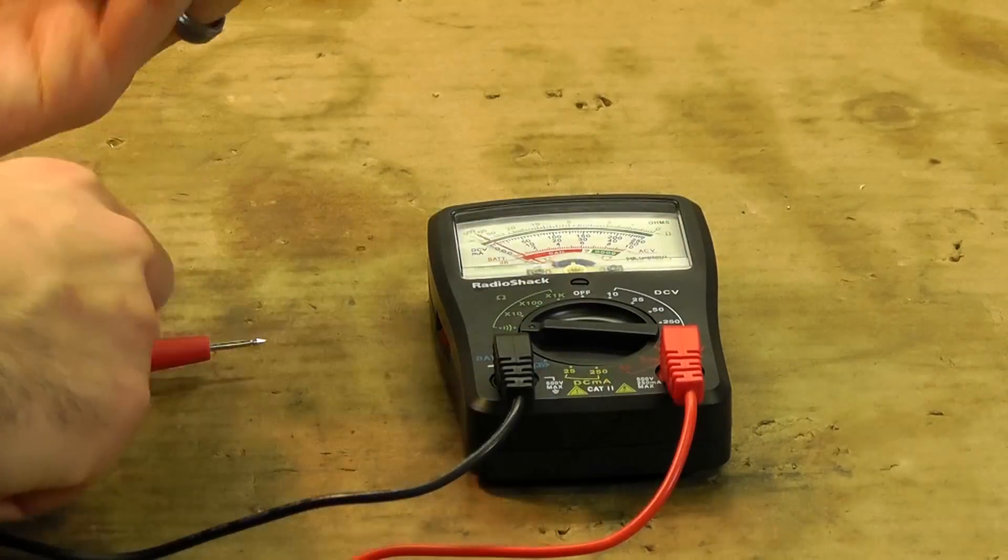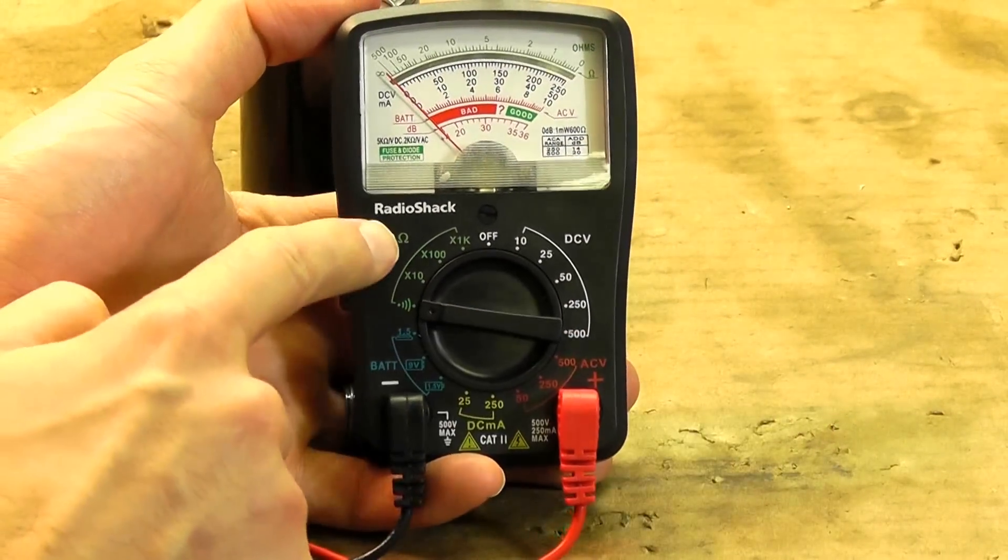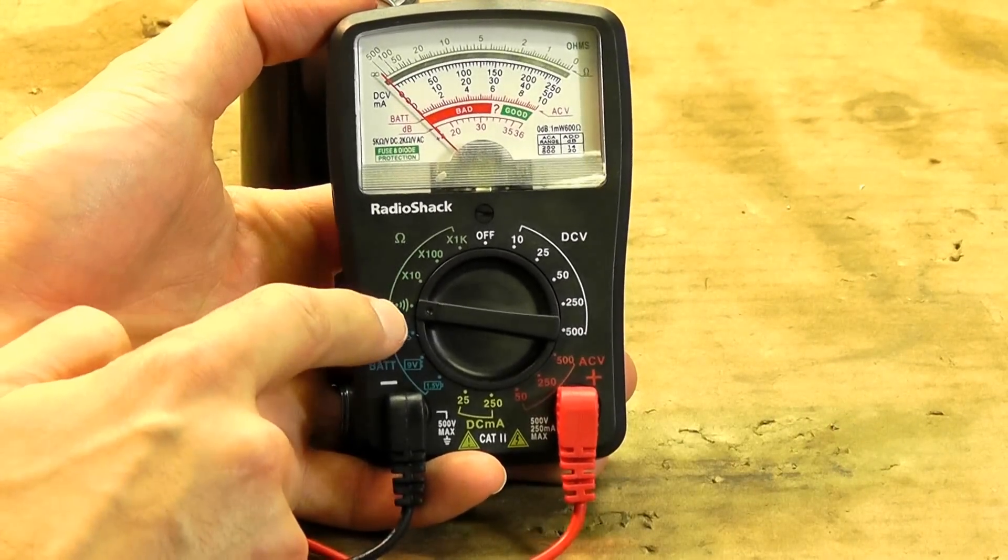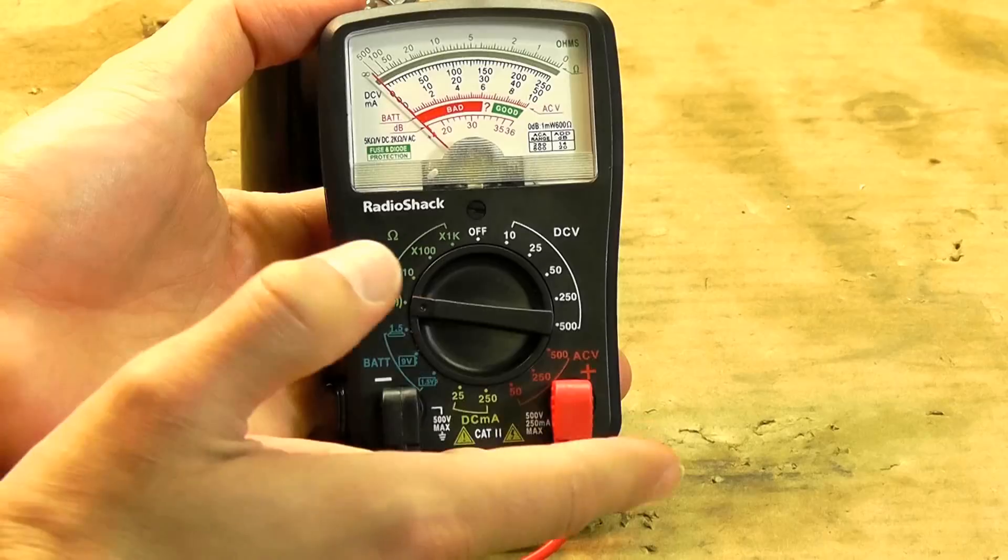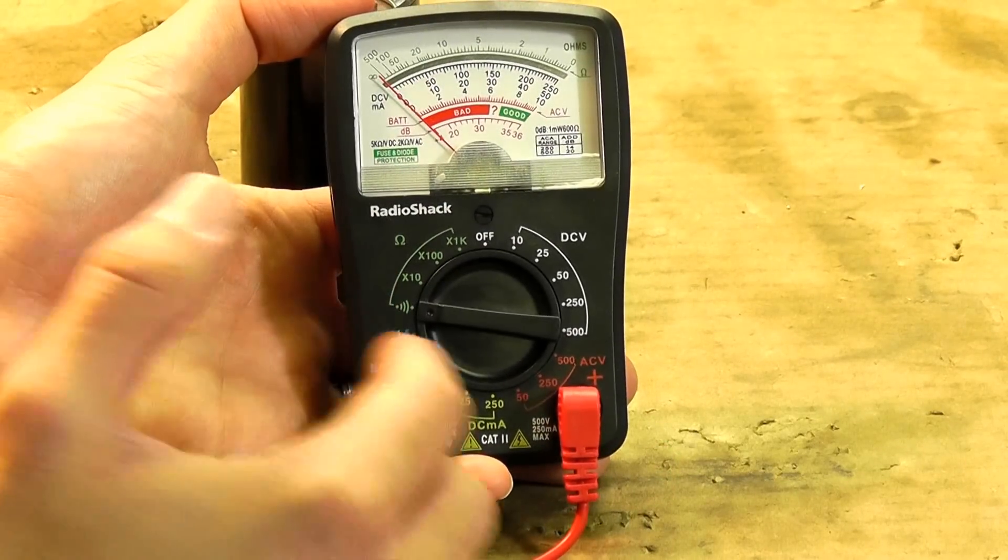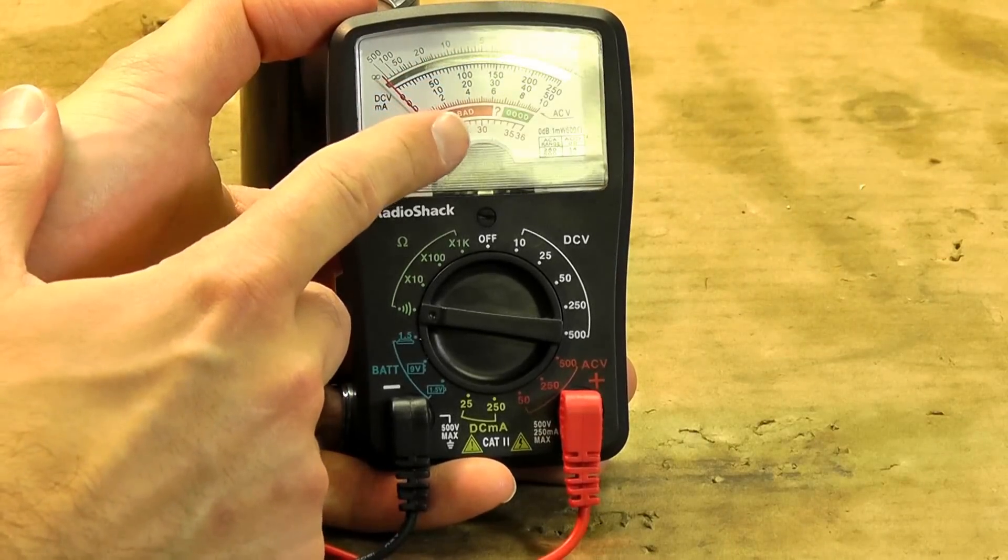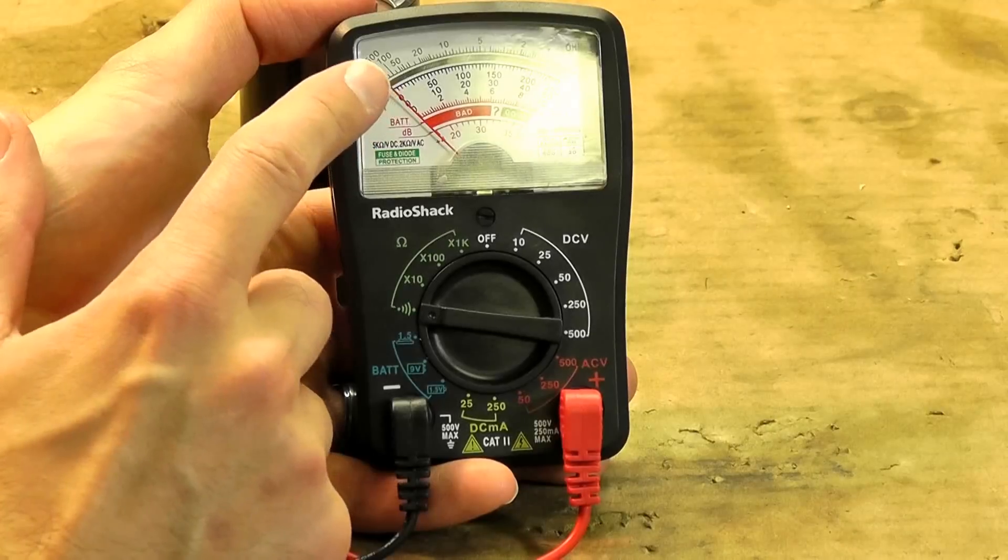We're going to take the voltage meter and set it on the ohm setting and on the audible setting so you can actually hear it when you touch both terminals, you'll hear a beep. And what this should do, being it's a good capacitor, the needle should jump up, spike up really quickly, not necessarily all the way to the right, however.